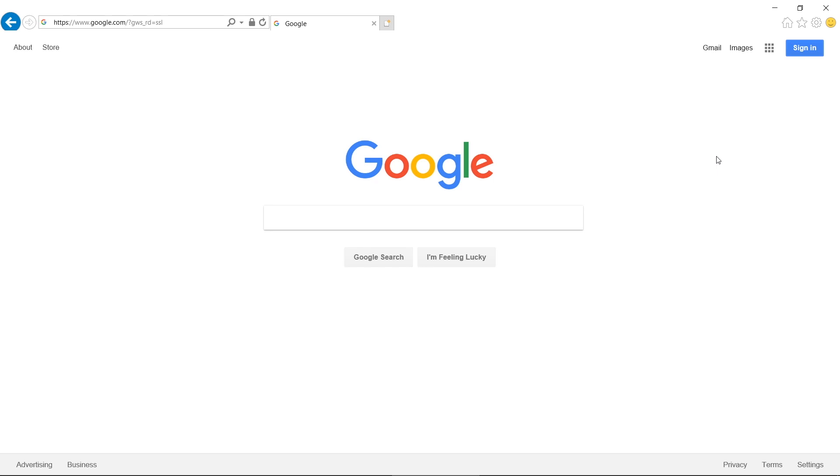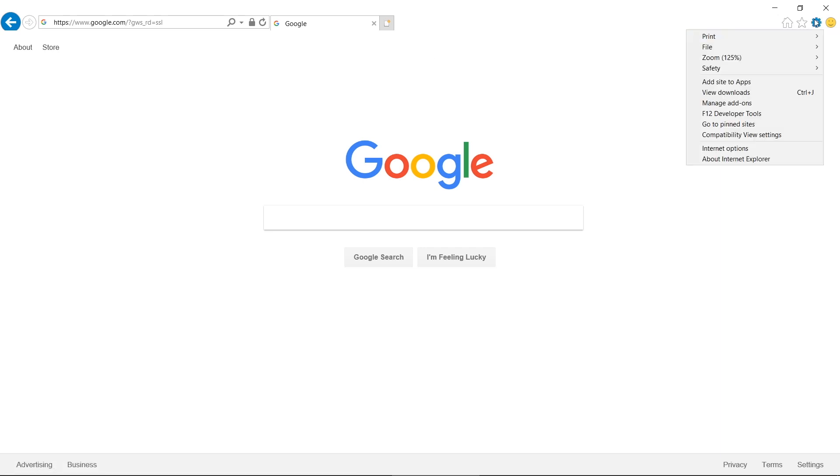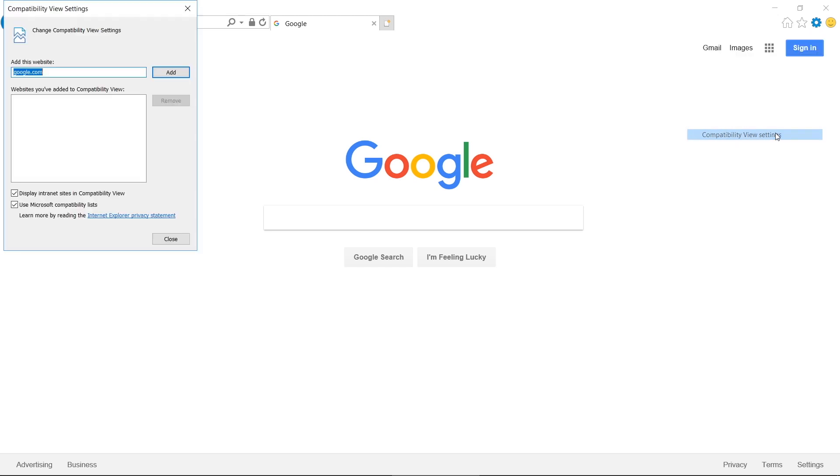After connecting, we can access the control by opening a web browser. Let's open Microsoft Internet Explorer 11. There's a quirk with Internet Explorer 11 and older. We don't need to do this with other browsers. Click on this gear icon and navigate to Compatibility View Settings. We need to uncheck this Display Intranet Sites in Compatibility View checkbox. Then click Close. If we don't do that, the programming software may not run properly. At this point, we can navigate to S&C Vista. This will bring us to the login screen.